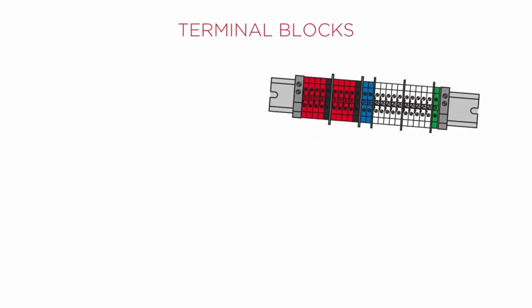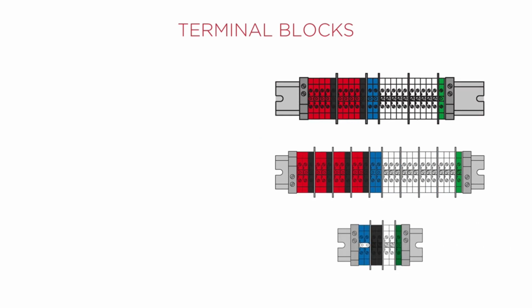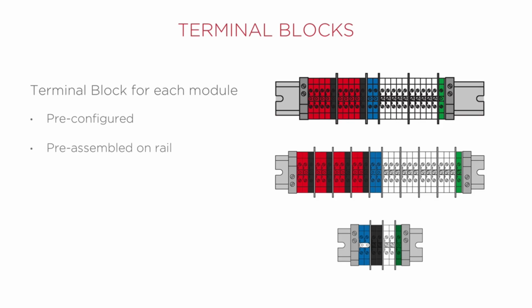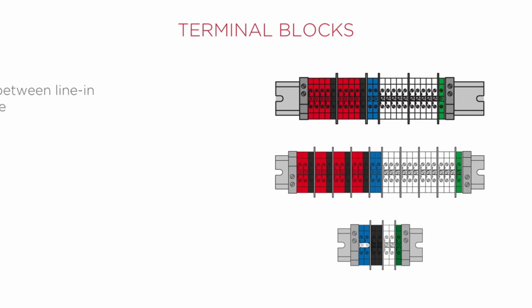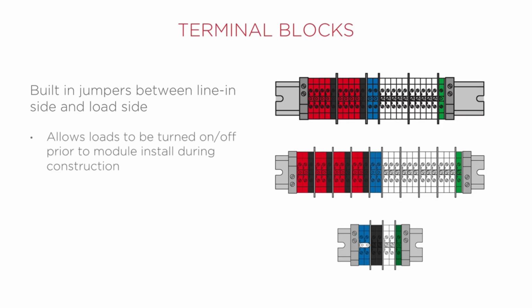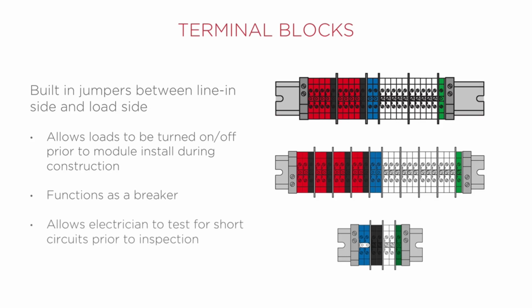The Control4 terminal blocks are similar to other manufacturers. Electricians who have done centralized lighting before will know what they are and how to install them. The terminal blocks are pre-configured, pre-assembled on the rail, and sold separately. They're generally purchased at the rough-in phase. The terminal blocks feature built-in jumpers between the line-in side and the load side, and allow the loads to be turned on or off prior to the module being installed during construction. The terminal blocks also function as a breaker between the circuit breaker and the fixture, allowing the electrician to test for short circuits prior to inspection.